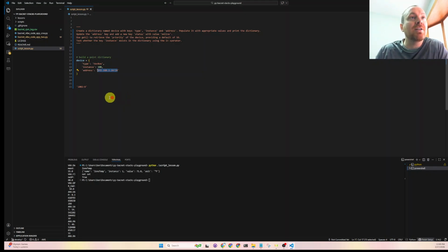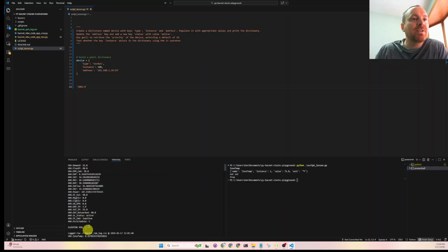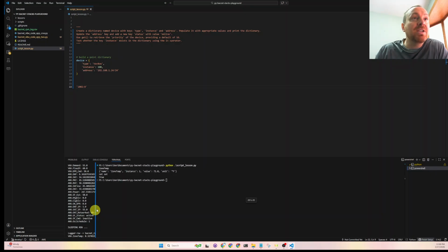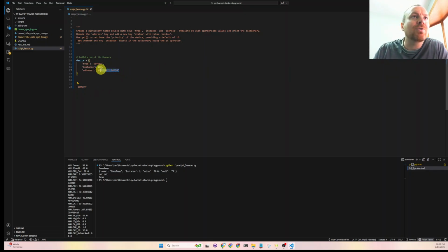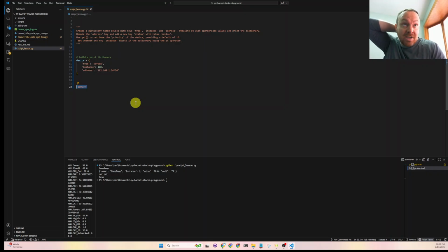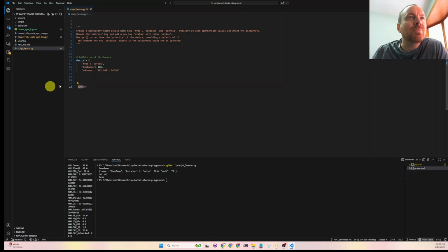Instead of an IP address, which is BACnet IP, a BACnet MSTP network is mostly old BACnet equipment. Most of the BACnet stuff is getting switched over to BACnet IP, but there's still a ton of 2-wire twisted pair networks out there, and their addressing in BACpypes and BAC0 would be something like this. I'm pretty sure I have that right. So it would be your MSTP network and then your hardware address.